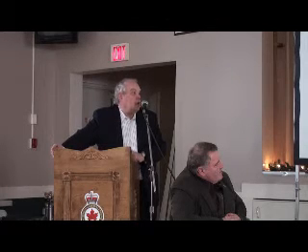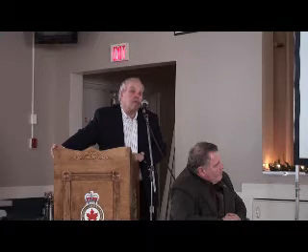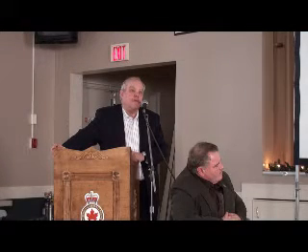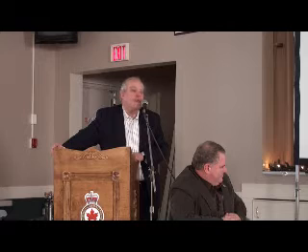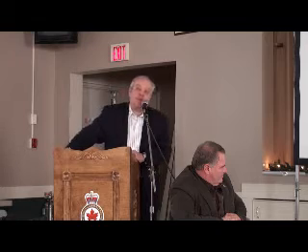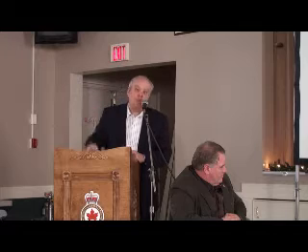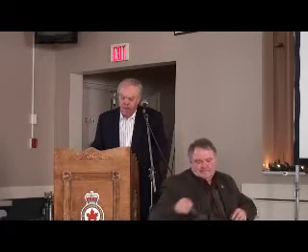And we found the manager saying that these systems have an audio and visual alarm when they fail. People tend to get annoyed with them when they go off, and consequently they either put a Tim Hortons cup on the visual light, or else they shut off the audio signal, which means that they have to more or less conduct a weekly inspection of all of these homes just to make sure that isn't happening and they fail. Next slide.